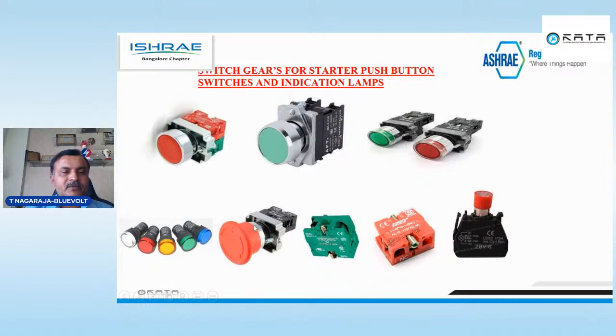For safety purpose, when you want to start remotely with an RPBS, remote push button station, if the motor is beyond 10 meters of the electrical panel, an RPBS should be used. That is an authority norm. Beyond 10 meters, whether the panel is visible or not, a remote push button station should be used with the lockable push button. If it is a DOL starter, you can use the isolator. If it is star delta, you can go with the remote push button stations.